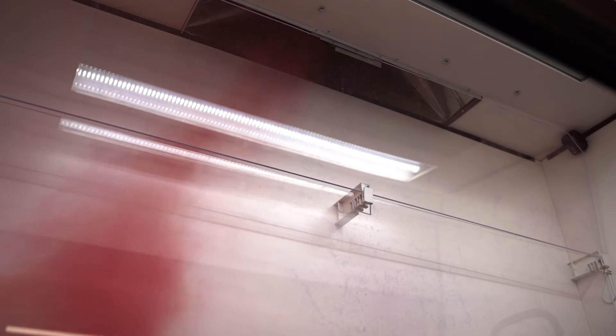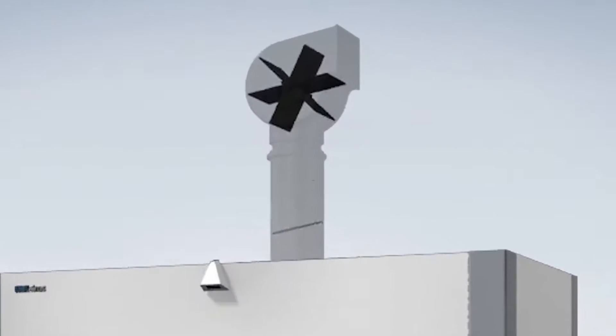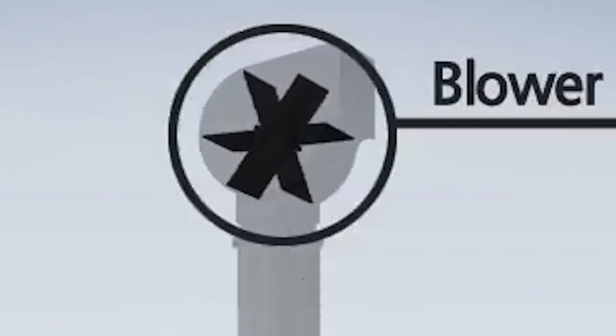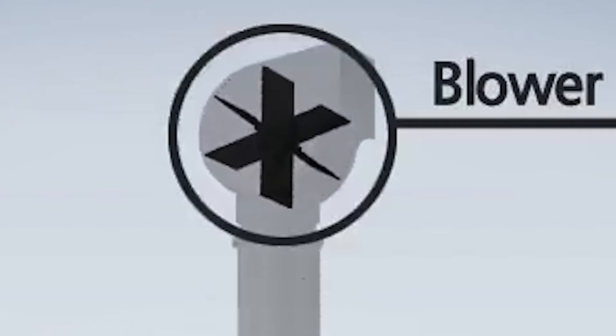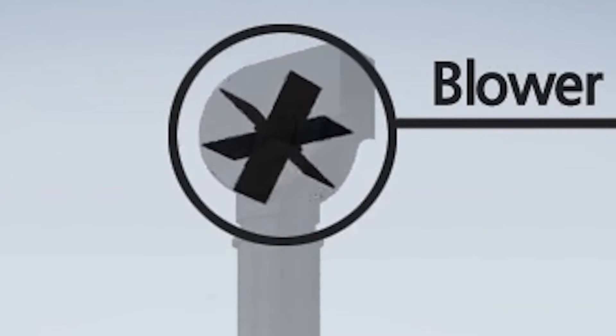There is an opening at the top of the plenum where the ductwork is attached, and then there's a fan — usually on the roof — that creates the lowest pressure for the entire system.